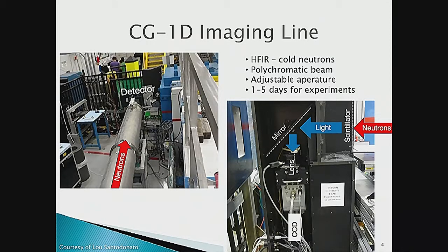So once they hit the scintillation detector, light is emitted, bounces off the mirror, and goes down to the CCD detector down here. This mirror and the CCD detector angle is important so we don't ruin the detector. This fencing is very important so that users don't get affected by neutron radiation or gamma radiation. And so you can't have 5 millirem outside of that fence line.